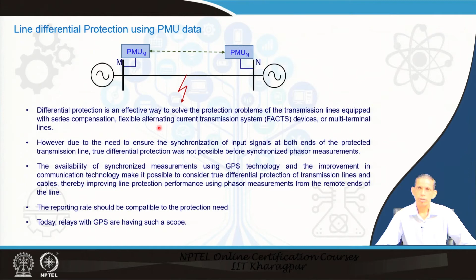Fault location we have seen from the travelling wave perspective. There we also mentioned that if we have synchronized data at both ends from PMU applications, fault location is an offline business, there is no issue of speed. So, in this case if we have a fault at x, then you can write from this side, for a single phase, simply a basic equation, and then you can extend to the 3 phase concept also. So, the Vm can be equal to Vf, the fault voltage here, plus this drop.